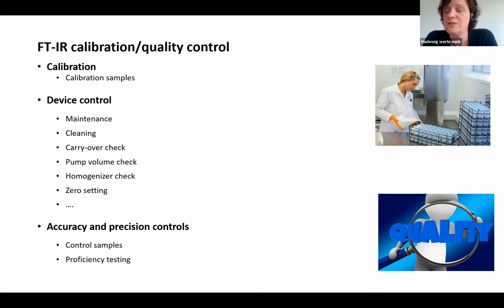Next to the calibration, several controls are necessary. The following controls are necessary on the device, such as maintenance, cleaning, carryover check, pump volume check, homogenizer check, zero setting, and so on. In addition, accuracy and precision checks are also necessary. Control samples and proficiency samples from the respective matrix can be used.